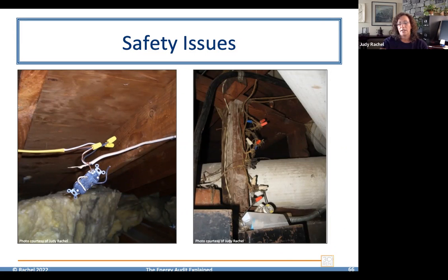So finding those kinds of things, and these once again are some of those non-negotiables: you can't put insulation over those non-insulation-contact-rated recessed lights. You can't be blowing insulation over uncovered junction boxes, and all these things. Those are non-negotiables that need to get fixed before you then say go ahead and blow insulation into an attic.